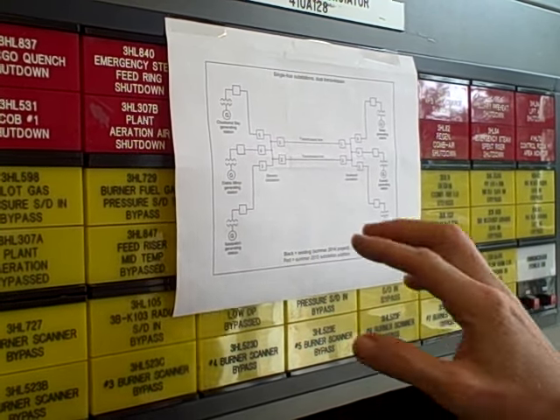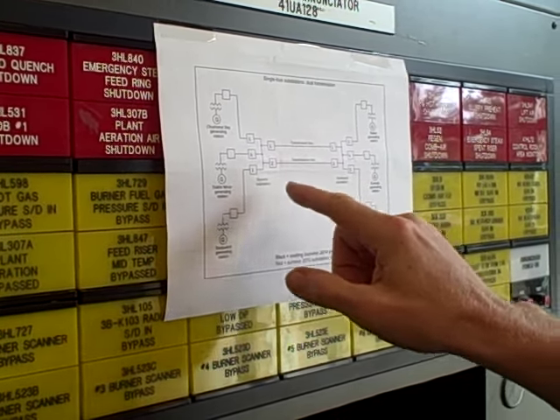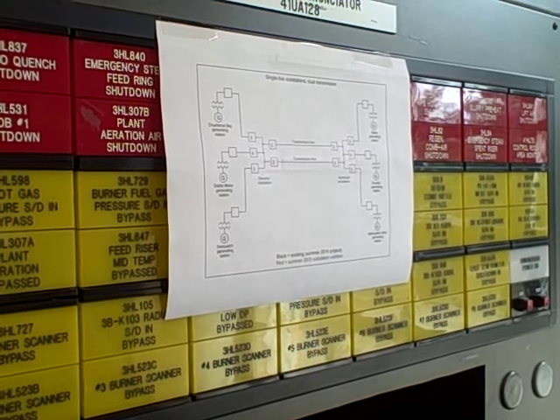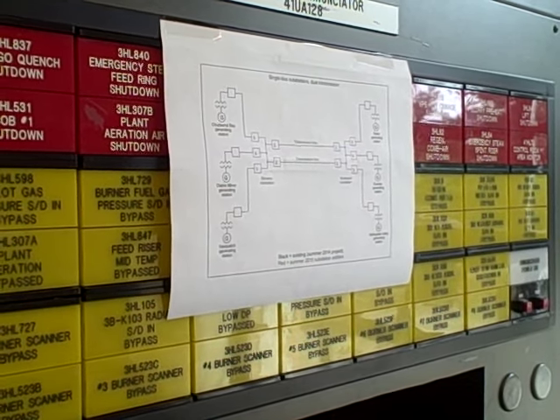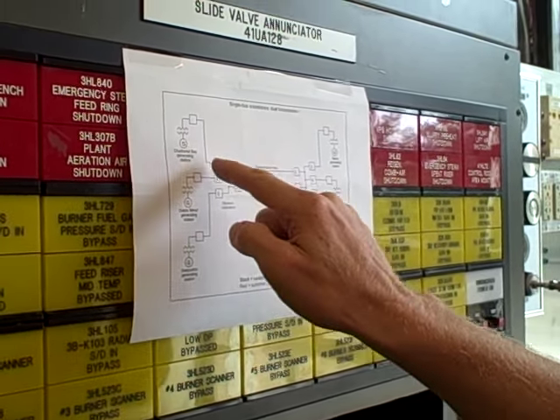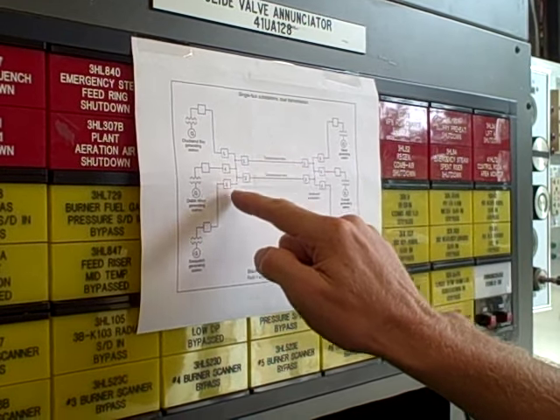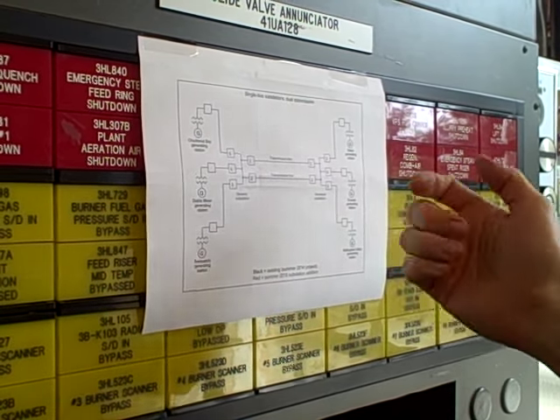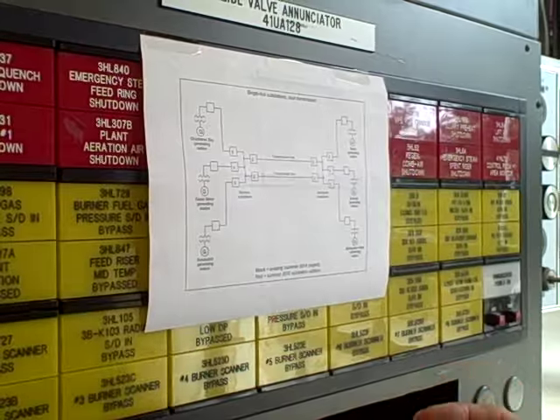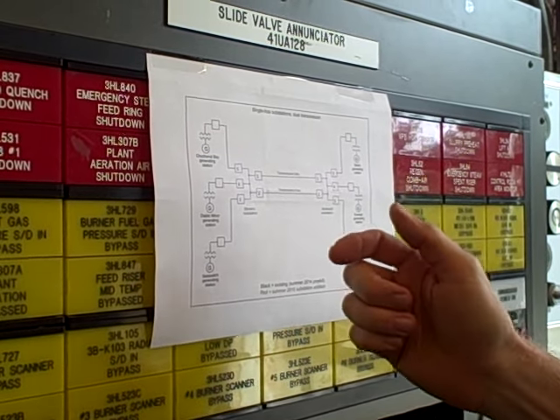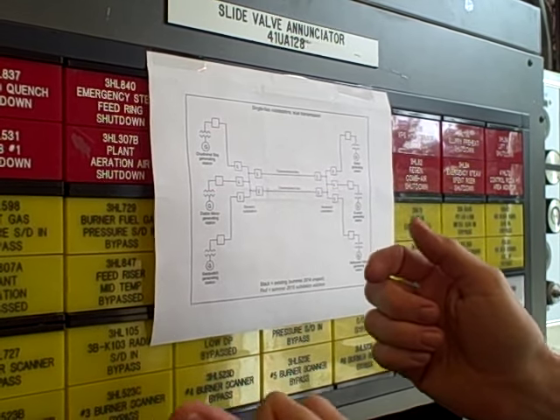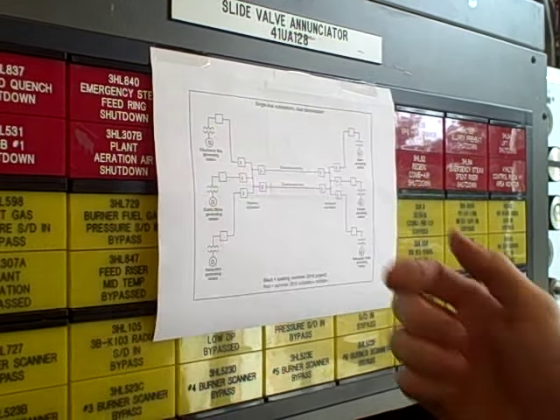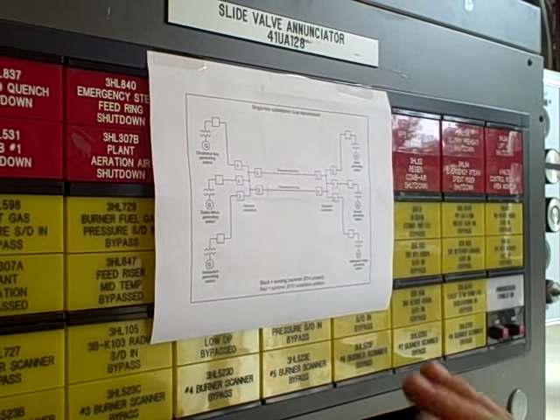This summer we equipped each of the substations with differential current protection on the bus, which basically means we're monitoring all the current going in and out of that common bus. And if there's a difference in current, for example, if we have current coming in that's not reflected coming out, we know we have some sort of fault within the bus and that differential relay will trip.